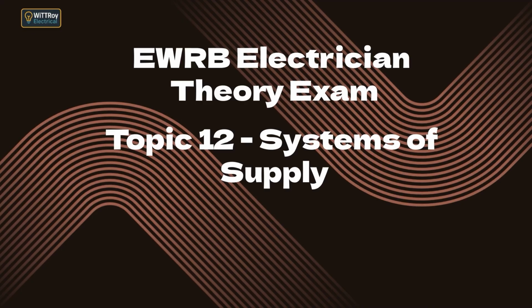12.1e. State the advantages of balancing the load over the three phases. Balancing the load across all three phases reduces neutral current, minimizes voltage drop, improves efficiency, reduces heating of supply equipment, and provides more stable voltage for consumers. A well-balanced system is safer and more reliable, and it reduces stress on the transformer and distribution network.